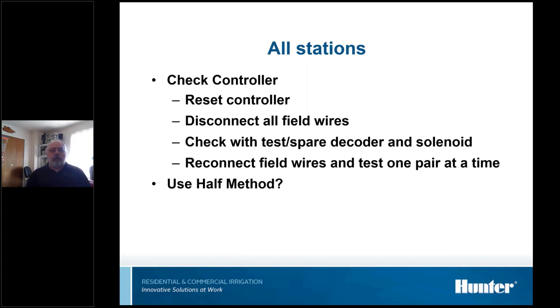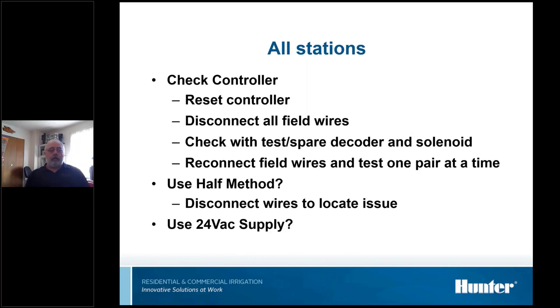Then there's a couple ways we can go. We'll use what we call the half method. This is the old school way of troubleshooting these systems. Basically, you're just going to disconnect wires to find problems. Or we're going to use a 24-volt power supply and a clamp-on ammeter to find the problem. Much faster, easier, cleaner way to do it. Anyways, here's how the half method works.